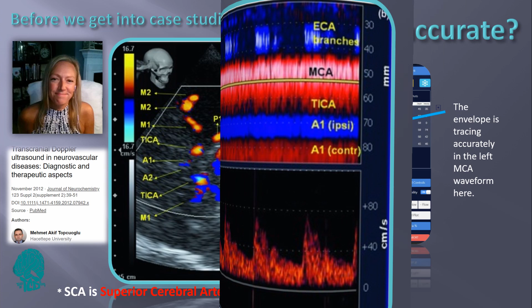One important thing to be aware of when looking at TCD and performing TCD in your facility is the envelope tracing over the top of the waveform. The envelope tracing is what is analyzing our mean flow velocities and our pulsatility index. This envelope tracing needs to be accurately hugging the waveform. So as we can see, this white line is not tracing accurately over the waveform on this side. This mean velocity of 82 and the pulsatility index of 1.06 is not accurate.